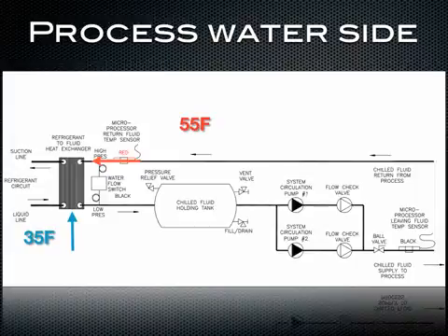The refrigerant temperature, if you look to the left of the drawing, is around 35 degrees F. So you have your 55 degree water coming into the evaporator. The refrigerant side is at 35 degrees, so that heat can transfer over from that 55 to the refrigerant side. Once that heat is transferred, it goes over to a different process and cycle, and that's in the other videos. Once that heat is removed, the evaporator will produce your 45 degree desired water temperature that's going to go back out to your process and cool your equipment.